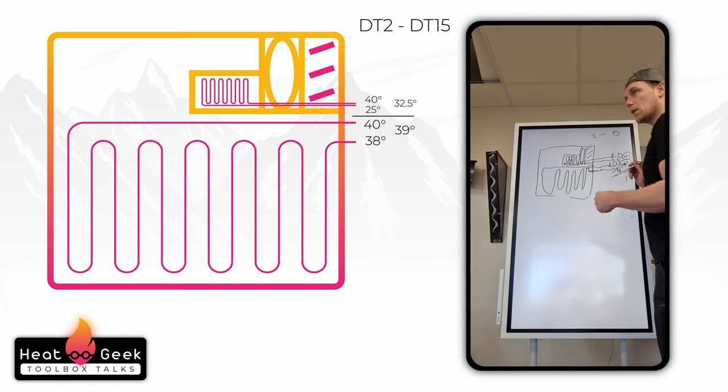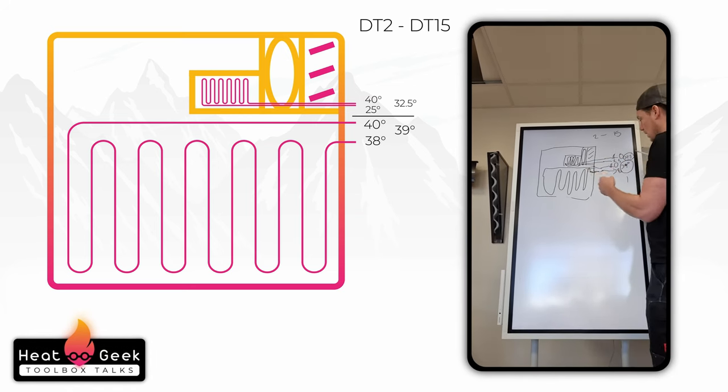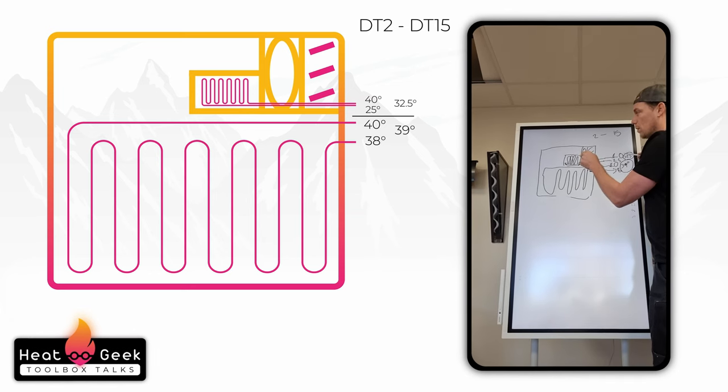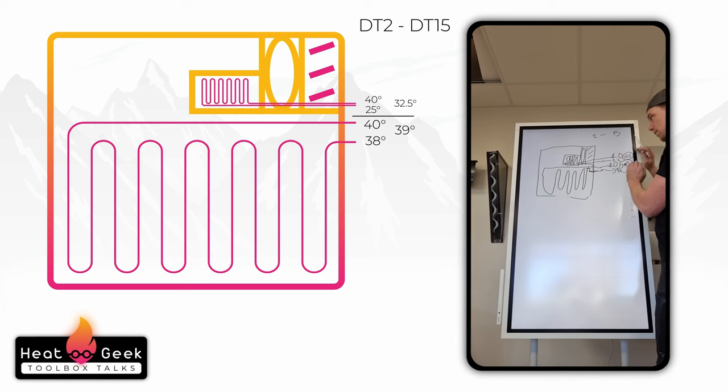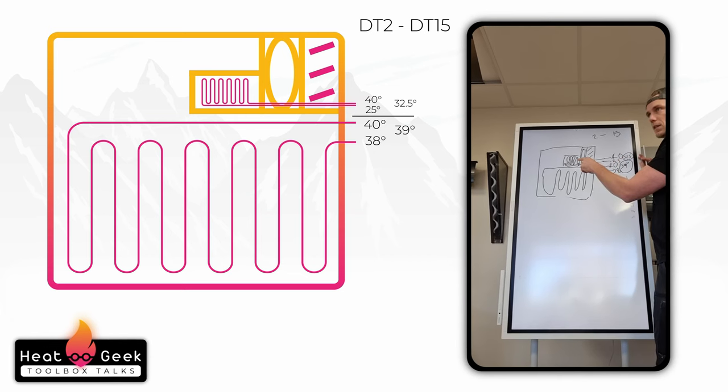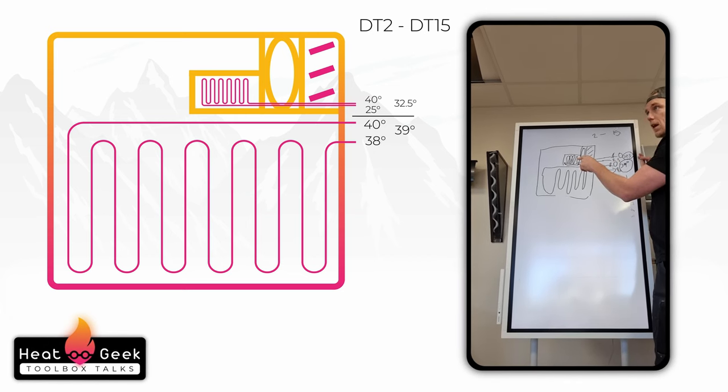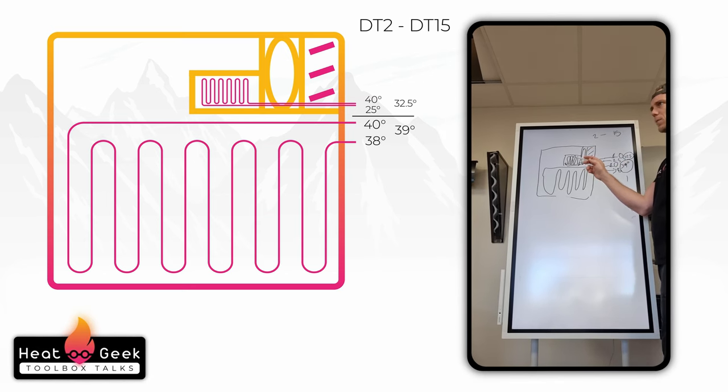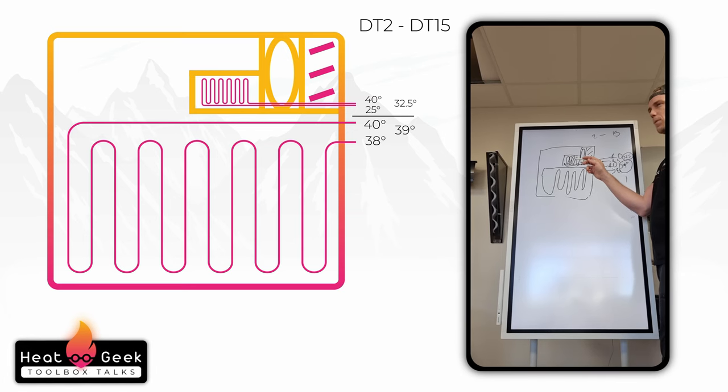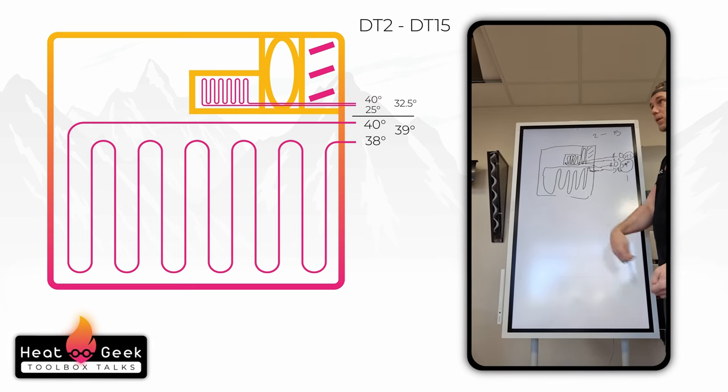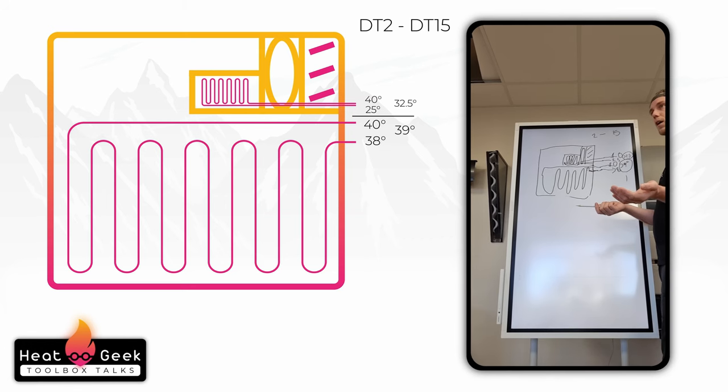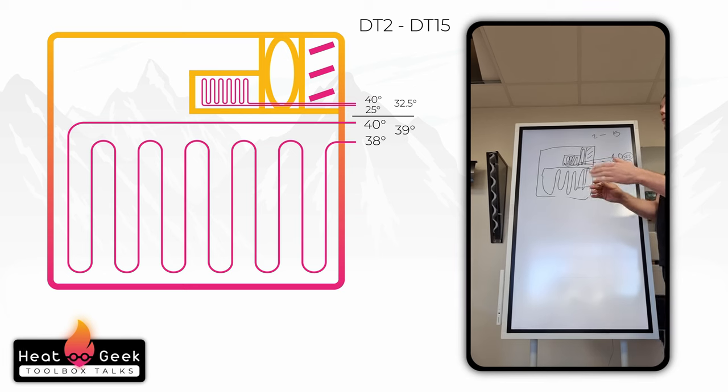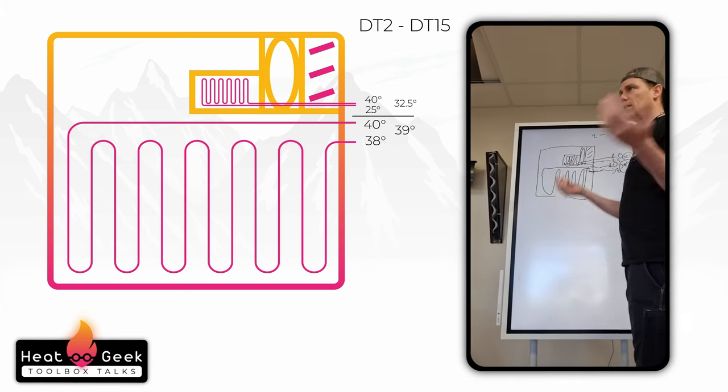You temperature limit with the stats. But let's say I had the same DT, you could cycle this on and off. I don't like cycling, so we play with the DTs, we get even finer tuning. That might turn off twice in a day even if it's oversized. In an extreme situation you might just go okay, let's just put 200mm centers in there, but I think that would be an extreme situation. That room choice could change in the future, it might become a heated room, so I'd still put 100mm, then you've got the choice of what temperature you want that room.